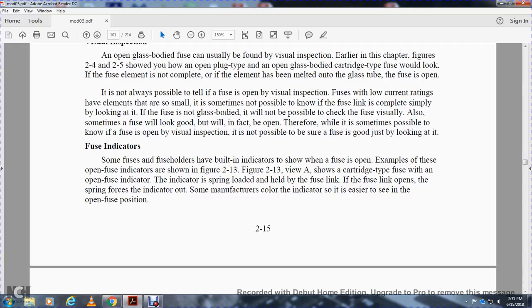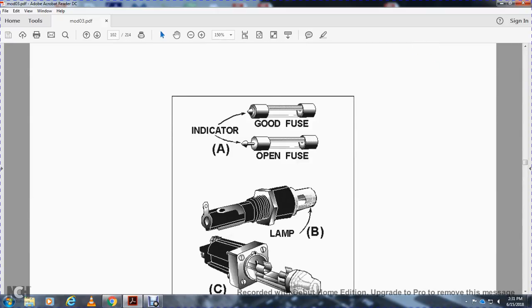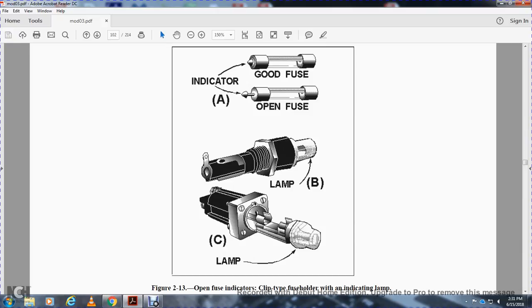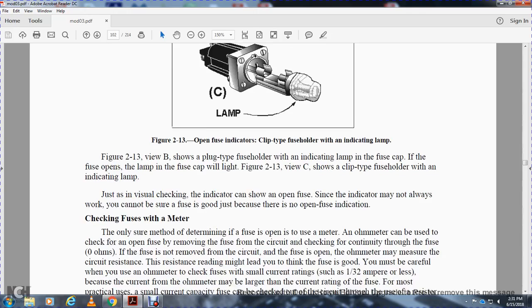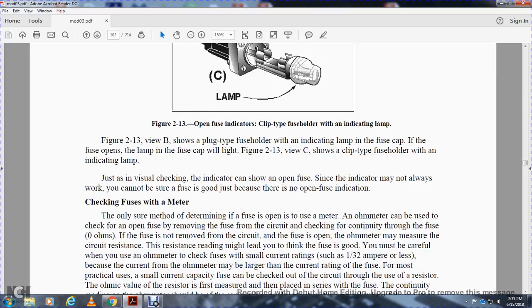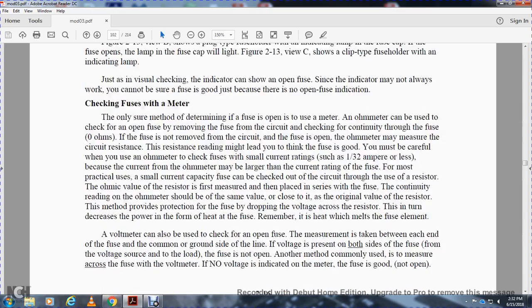Figure 2-13, View A shows a cartridge type open fuse indicator. A spring-loaded indicator - when the fuse link opens, the spring forces the indicator to pop out. Some manufacturers' indicators are so small that they may be difficult to see. View C shows a clip type fuse holder with an indicating lamp. The visual checking indicator can show an open fuse, but the indicator does not always work, so you cannot be sure there is no open fuse based solely on the indicator.